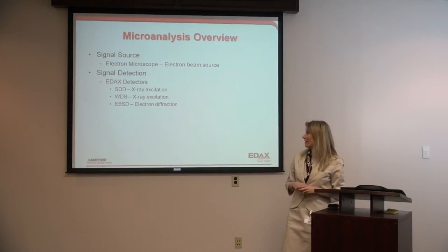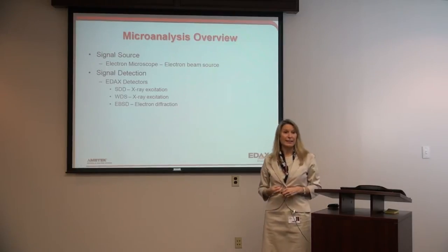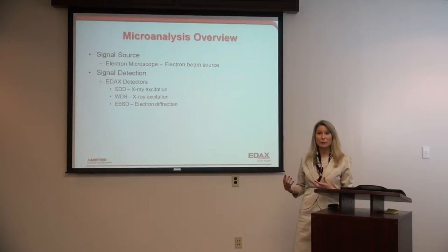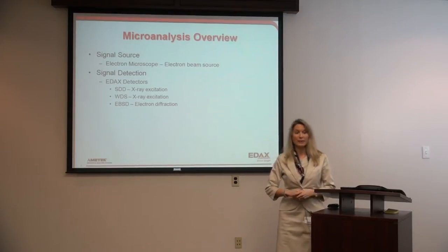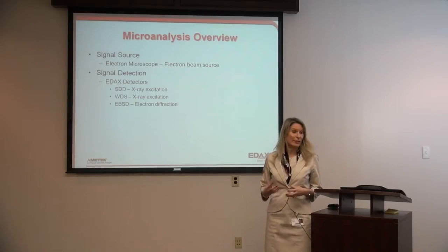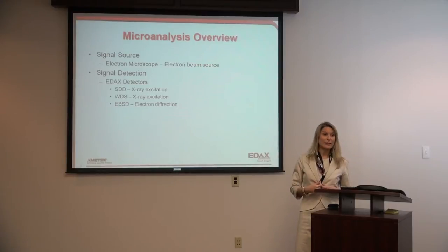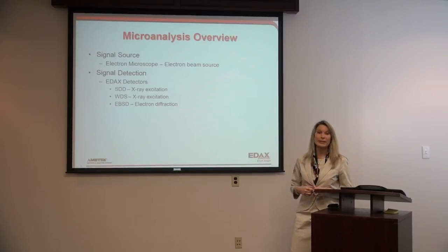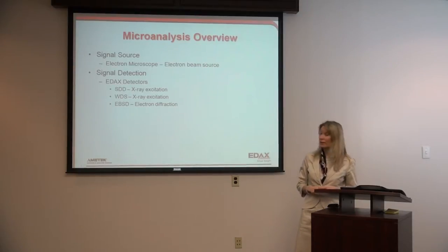Our SDD detectors, or our EDS detectors, detect X-ray excitation. That's an excitation event where the electron beam hits the sample with high force and generates an excitation event, which is an X-ray. With our EDS detectors, we analyze the energy of that X-ray. With our WDS detectors, we analyze the wavelength of that energy. That's the result of the electron beam to sample interaction.